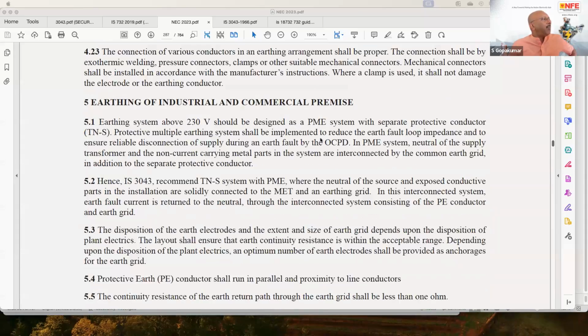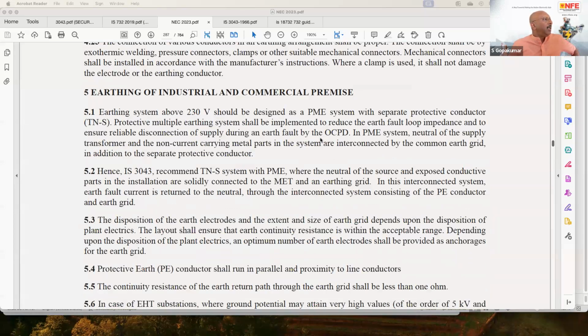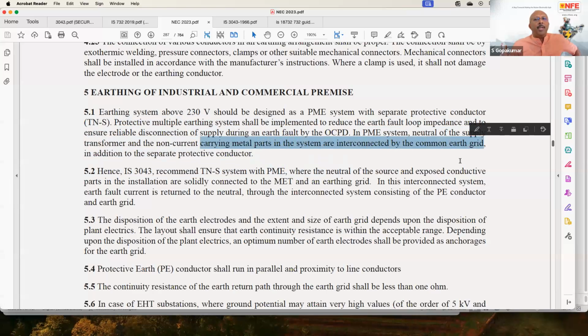Here it is coming under clause number 5, earthing of industrial and commercial premises. So an earthing system above 230 volt should be designed as a PME system with separate protective conductor. Now PME, protective multiple earthing system, shall be implemented to reduce the earth fault loop impedance and to ensure reliable disconnection of supply during an earth fault by the OCPD. So basically, this is already recommended in the standard. In a PME system, the neutral of the supply transformer and the non-current carrying metal parts in the system are interconnected by a common earth grid. This interconnection is actually missing. So these words are actually copied from IS 3043. It is not new wording in the standard. It was already existing.